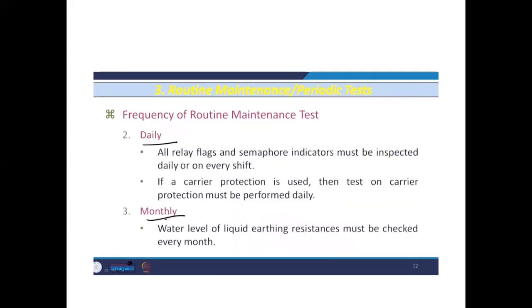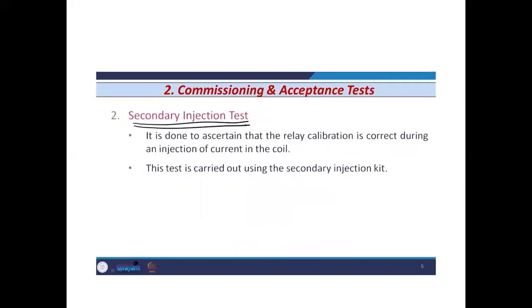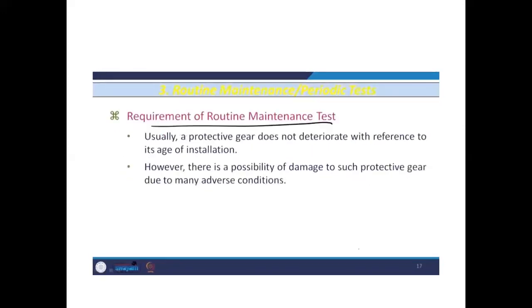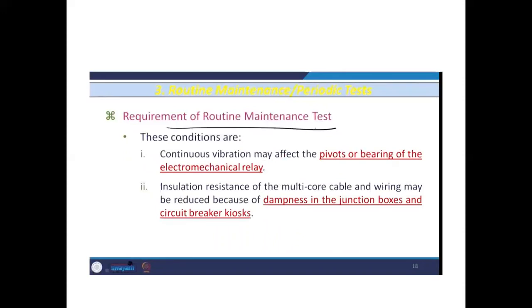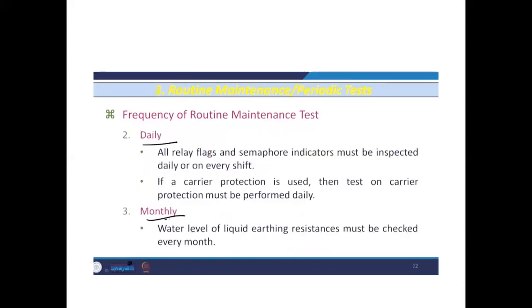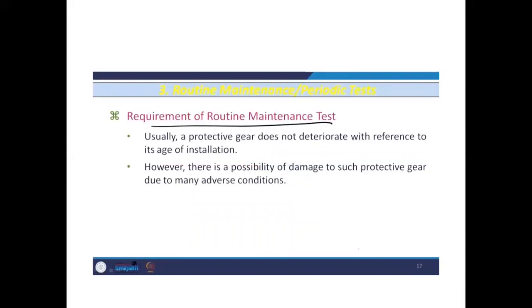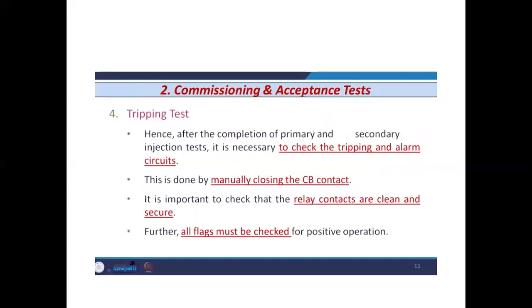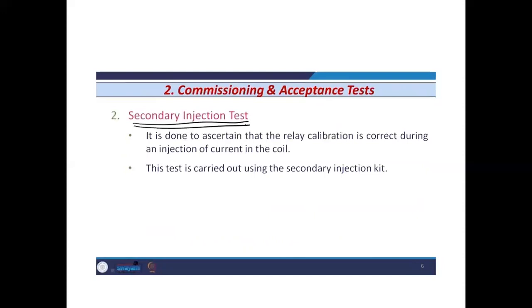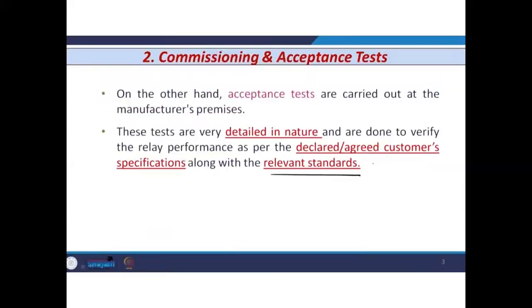Okay, so all that was about the commissioning and acceptance tests, and then we discussed the routine maintenance or periodic tests. In the earlier class we discussed the type tests, which were performed by the manufacturers. And now these commissioning tests should be performed to check whether these are according to the customer's specification or as per their demands, and whether they are meeting the IEC standards or not. If they are not meeting the IEC standards, then they are not acceptable.